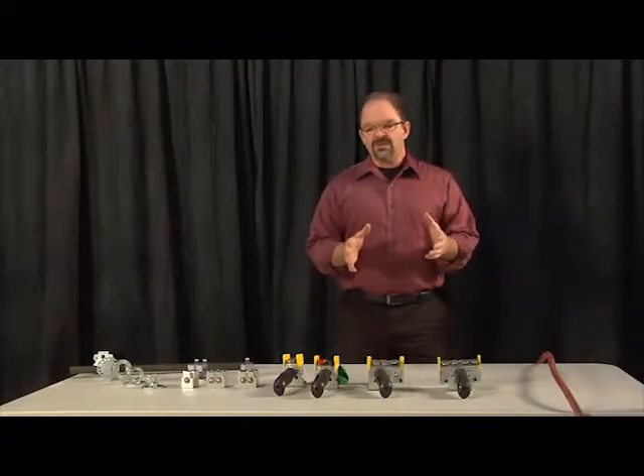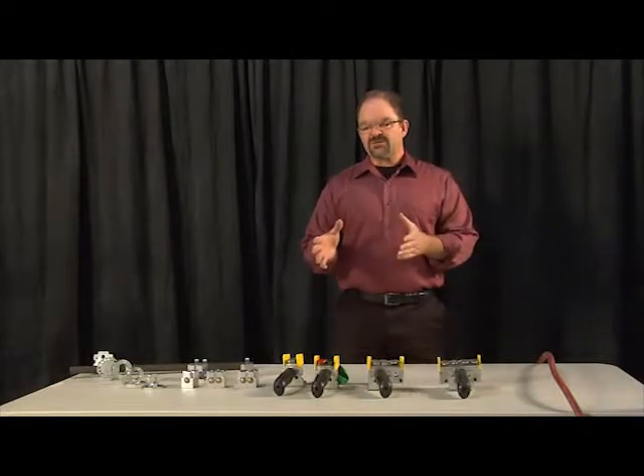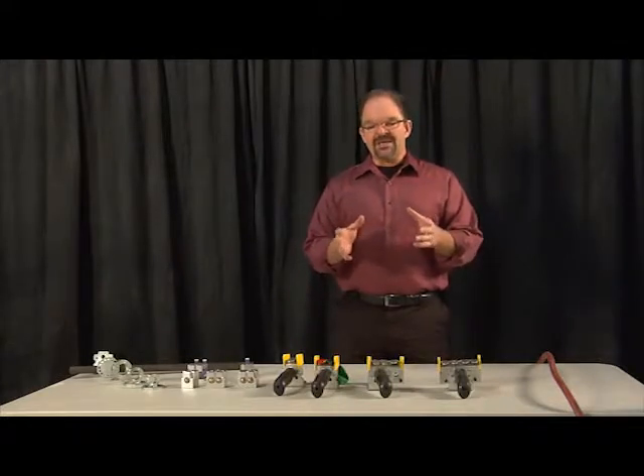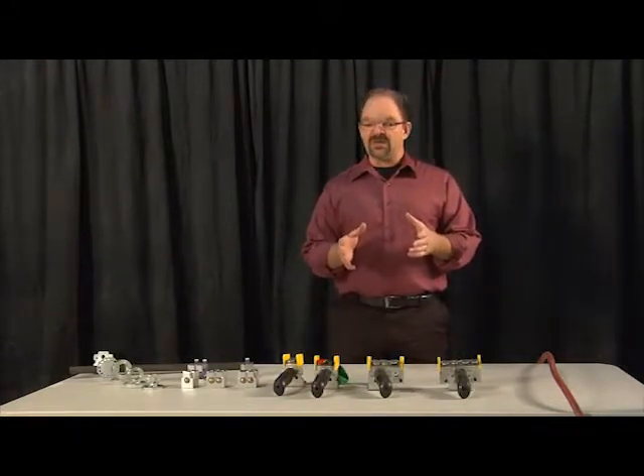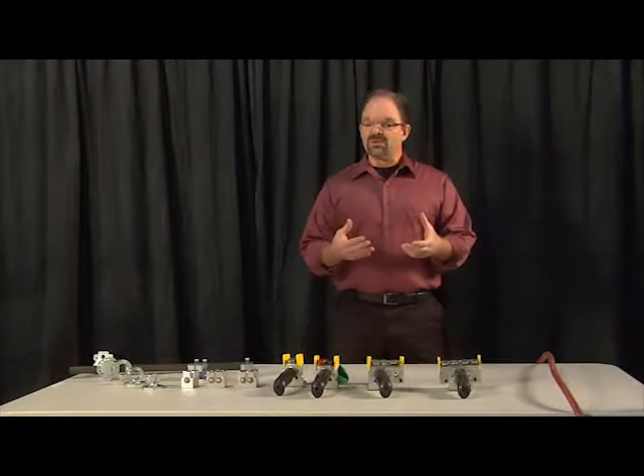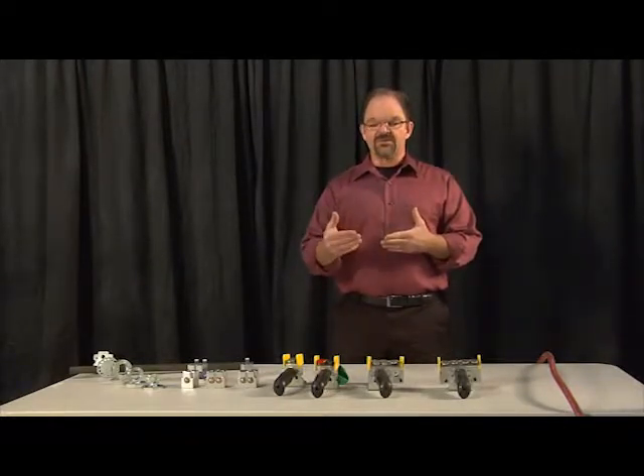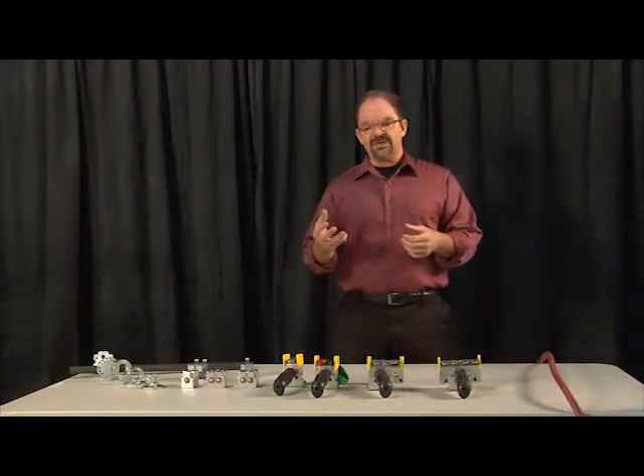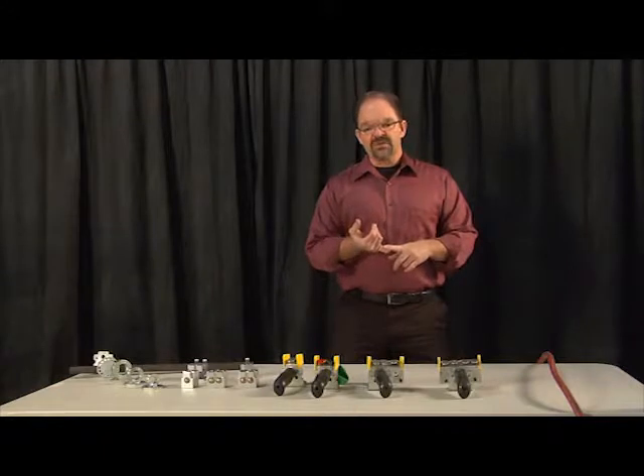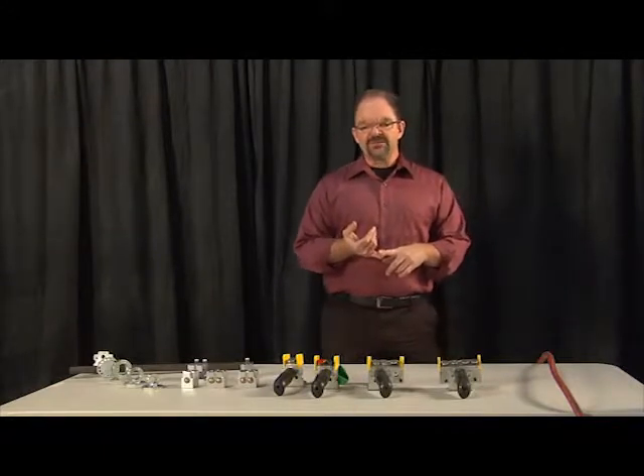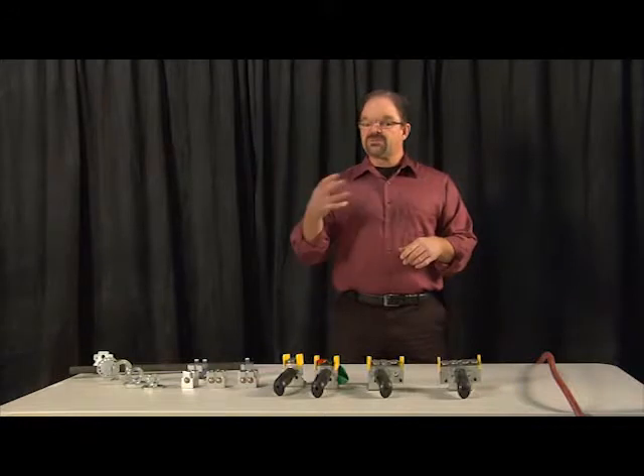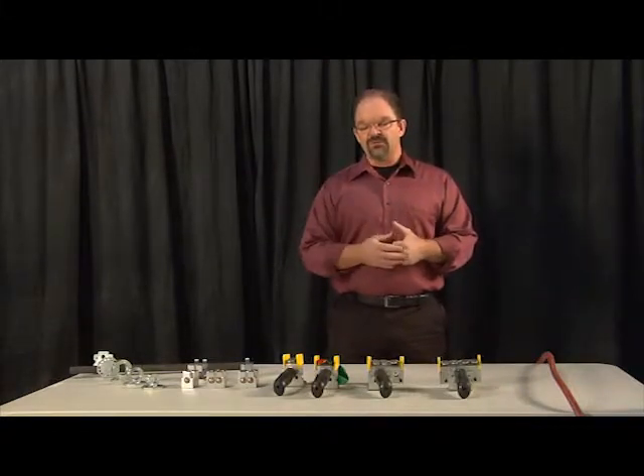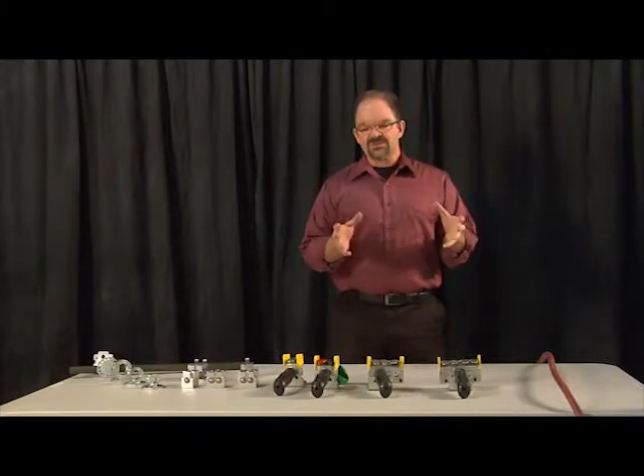Real quick, I want to talk about the technical specifications for the electric and pneumatic blocks. The pneumatic blocks are rated for 19.5 CFM at 90 PSI. They're mainly for piloting other devices. You're going to have to pilot a larger valve if you need very high flow. On the electric side, the switches are rated for up to three amps at 24 volt DC, and one and a half amps up to 240 volts AC.